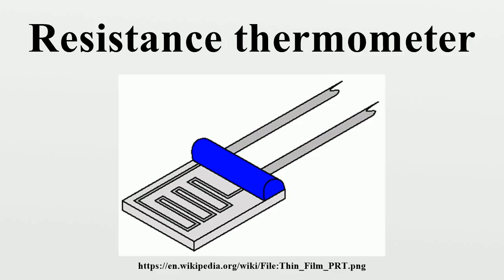Fixed-point calibration, used for the highest accuracy calibrations, uses the triple point, freezing point or melting point of pure substances such as water, zinc, tin, and argon to generate a known and repeatable temperature. These cells allow the user to reproduce actual conditions of the ITS 90 temperature scale. Fixed-point calibrations provide extremely accurate calibrations. A common fixed-point calibration method for industrial-grade probes is the ice bath. The equipment is inexpensive, easy to use, and can accommodate several sensors at once. The ice point is designated as a secondary standard because its accuracy is plus or minus 0.005 degrees Celsius, compared to plus or minus 0.001 degrees Celsius for primary fixed points.